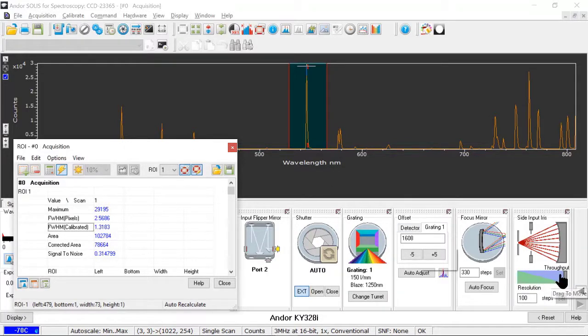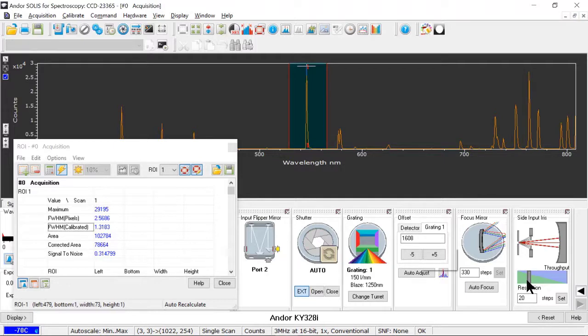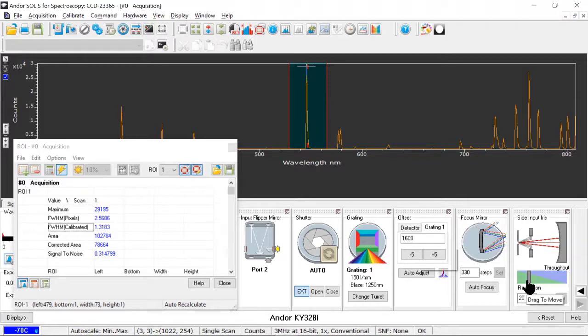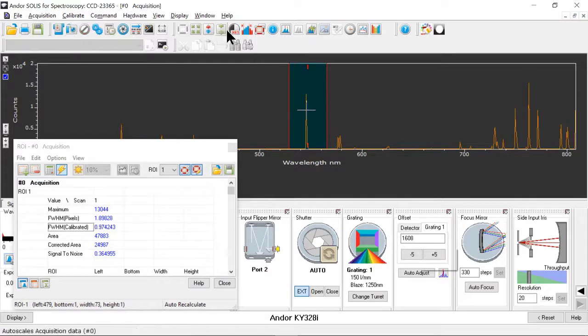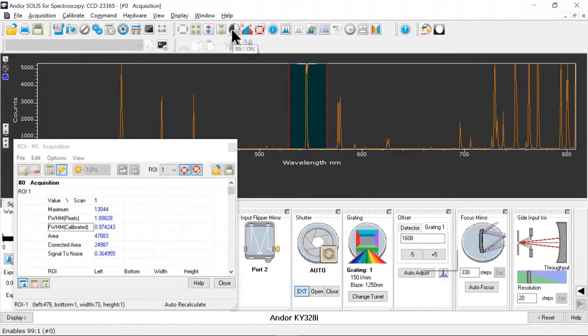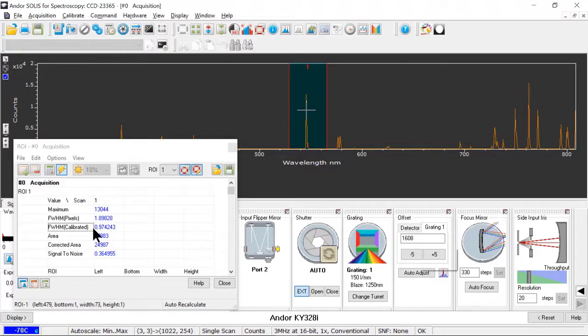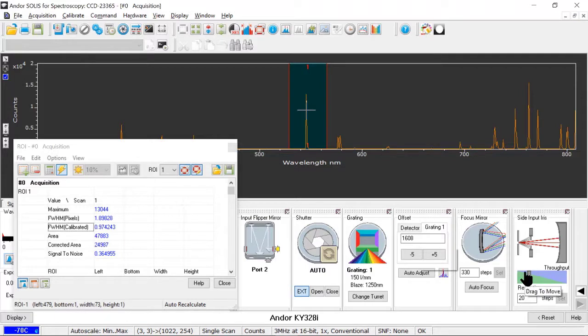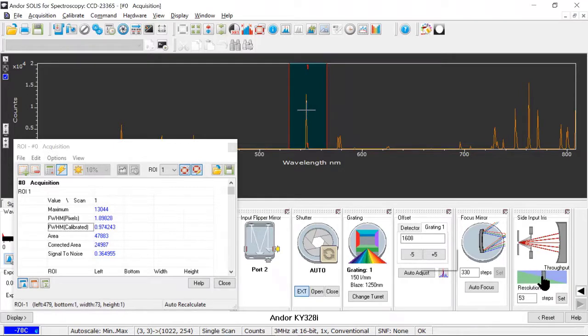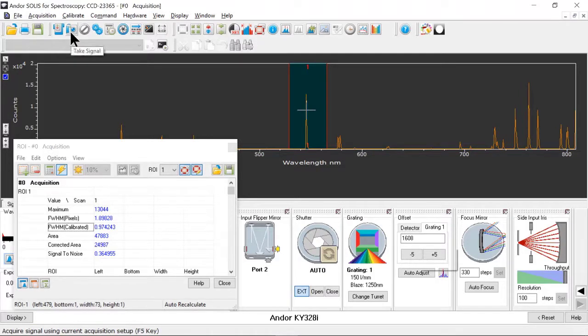When I restrict this iris, I'll drop this down to about 20 counts. It will act like a much longer focal length spectrometer. And when I take another acquisition here, you can see that the spectral lines have narrowed visibly. And as well, we're down to below one nanometer resolution here. We don't have to use this. We can keep this open all the time. But when we have a relatively bright sample that we require higher resolution from, this can be quite useful. I'm going to open this back up. And our original throughput and resolution is restored.